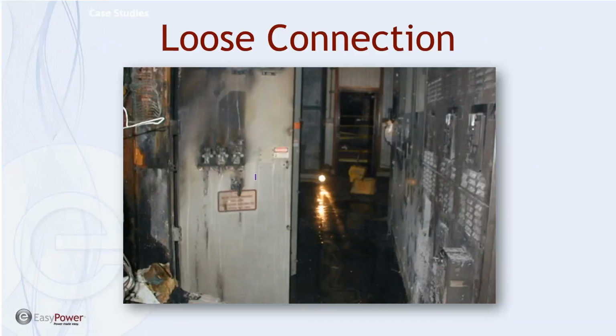A loose connection caused this kind of thing. So when you think about something like this and what the effect is, say nobody got hurt or anything like that, this is outage time. This is not going to be an hour or a day or maybe a week. This may be weeks and weeks of replacement, of getting switchgear replaced, and how much that's going to affect productivity and the products. It's going to be a tough thing to justify with the people up above.